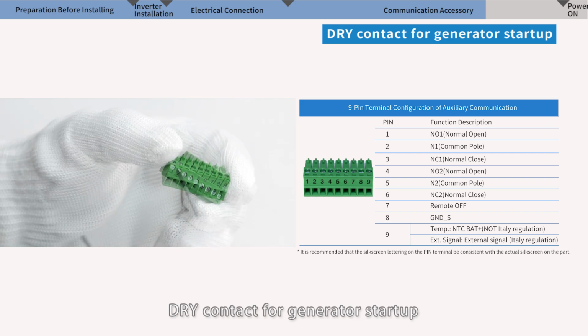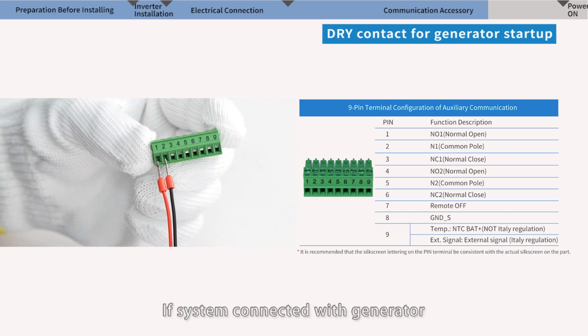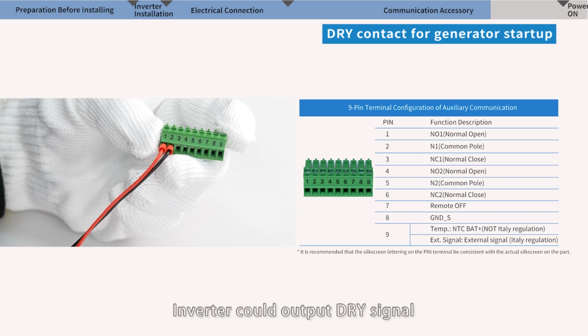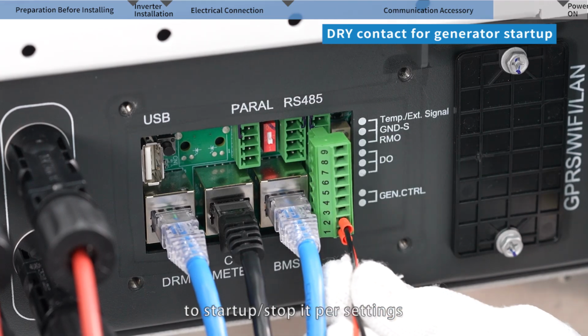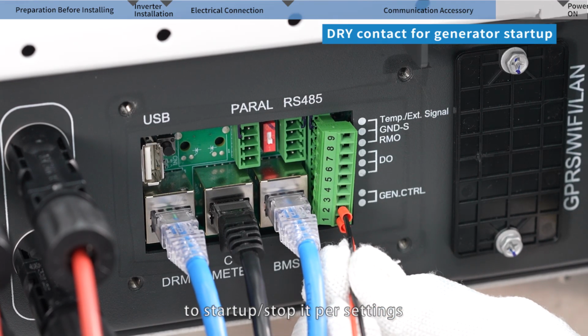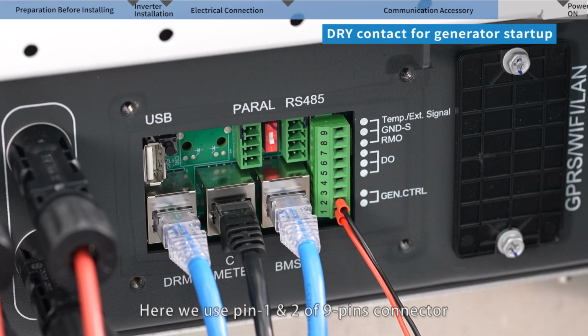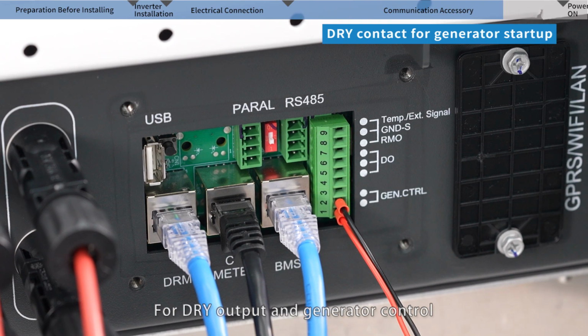Dry contact for generator startup. If the system is connected with a generator, the inverter can output a dry signal to start up and stop it per settings. Here we use pin 1 and 2 of the 9 pins connector for dry output and generator control.